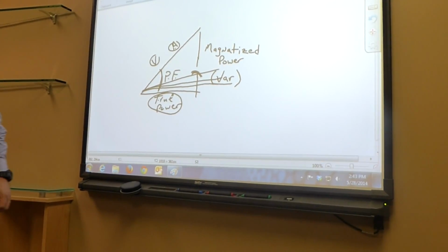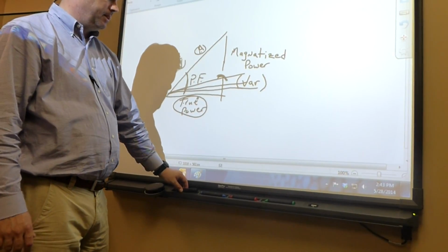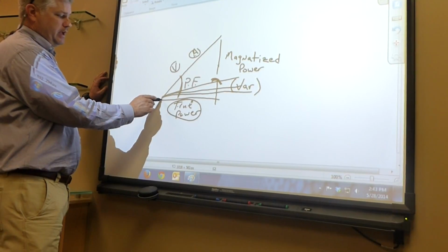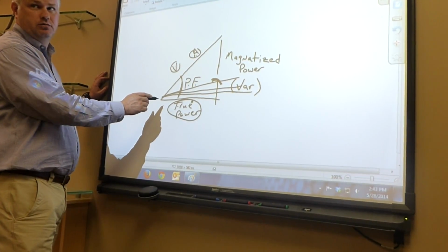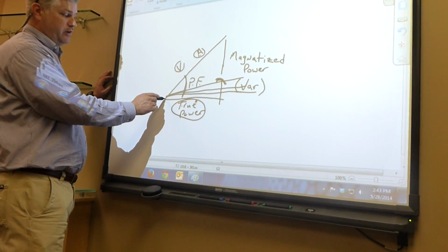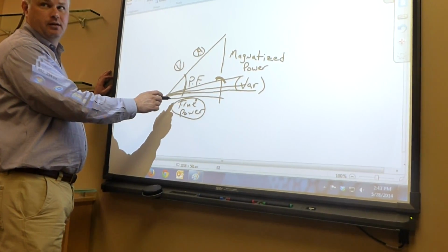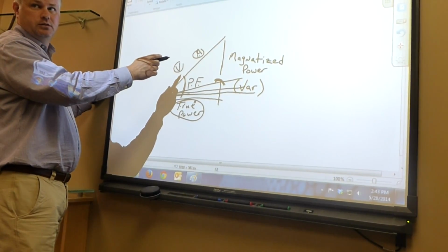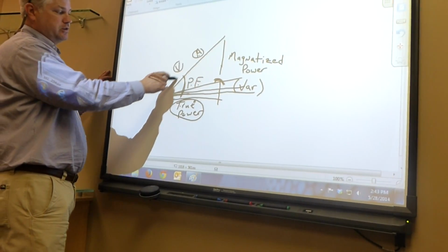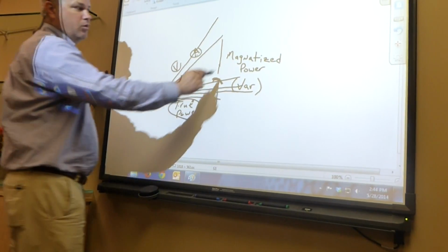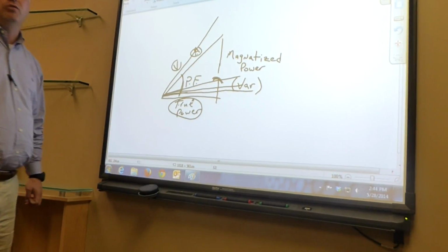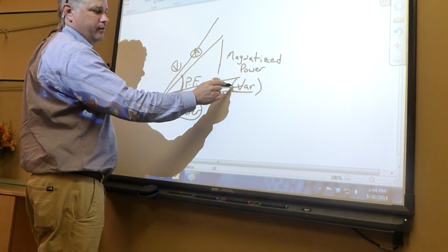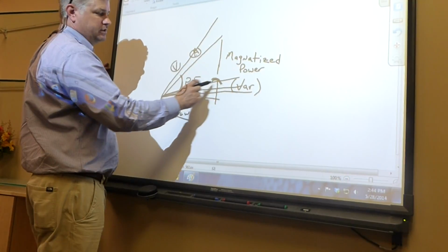You can do it, but it may not have an effect. Yeah, because if you miscalculate, either way you're going to manipulate this angle. If you calculate correctly, you're going to lower it. If you don't calculate correctly, possibilities are it doesn't change at all, the angle's unaffected, or the angle goes the opposite. How could it go the opposite? Oversized. You oversize it. Because if this isn't correct and this is oversized, it's going to have the opposite effect.